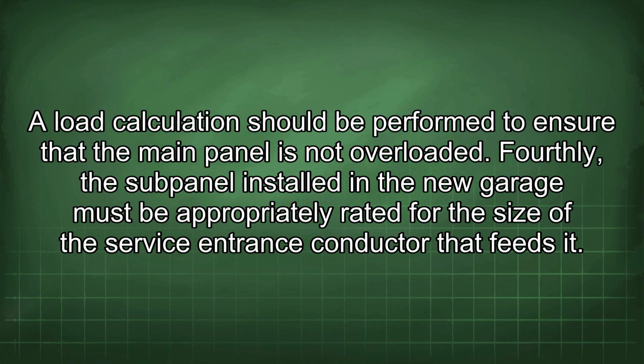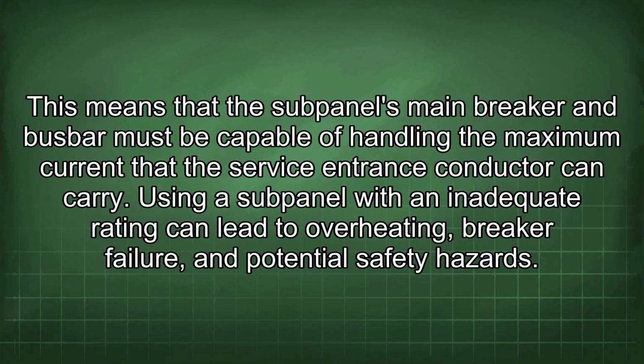Fourthly, the subpanel installed in a new garage must be appropriately rated for the size of the service entrance conductor that feeds it. This means that the subpanel's main breaker and busbar must be capable of handling the maximum current that the service entrance conductor can carry. Using a subpanel with an inadequate rating can lead to overheating, breaker failure, and potential safety hazards.